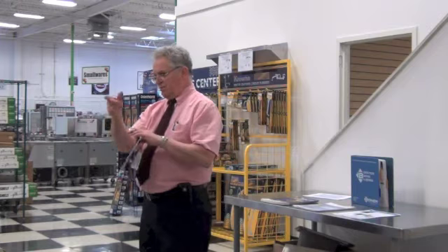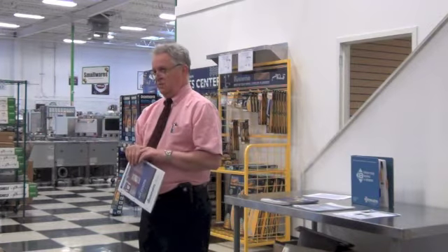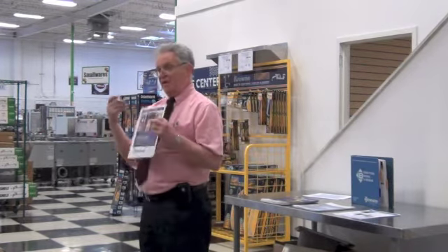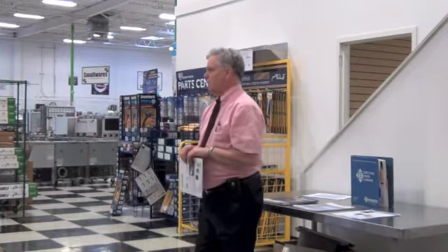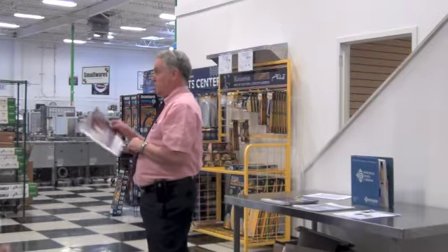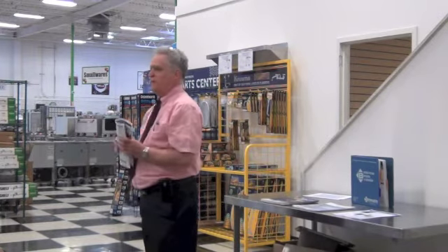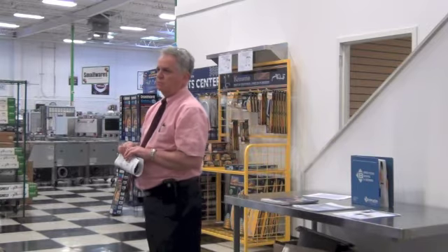The next thing you need to know is your switches. The normal switch is a plunger, like your refrigerator door. You open the door, that switch pops out, and the light turns on. In this case, the switch pops out and the air door comes on. My preference is that you use it that way, so that every time the door opens, the air curtain comes on. It's required in California in every food service application. North Carolina health inspectors are pushing it very hard. Other health areas do not require it as much. California, it's a law for the state. You must have an air door on your receiving door.